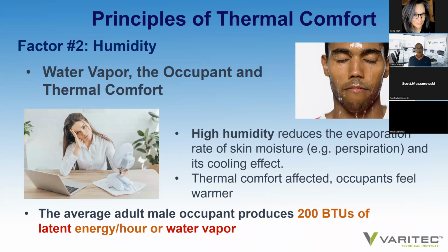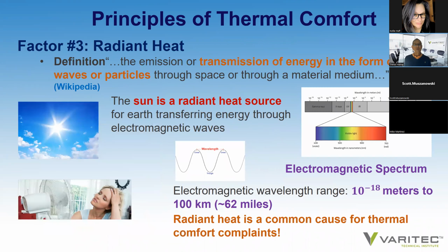So what about humidity, water vapor, the occupant, and thermal comfort? Well, humidity is related to human comfort because a high humidity condition reduces the evaporation rate of skin moisture or perspiration and prevents our own personal human air conditioning system from operating effectively. So thermal comfort is affected the more humid an environment. Occupants feel warmer because their bodily cooling system is not operating effectively. So that is how humidity impacts thermal comfort. The average adult male occupant produces about 200 BTUs of latent energy. So that's quite a bit of moisture that an occupant can add to a space.